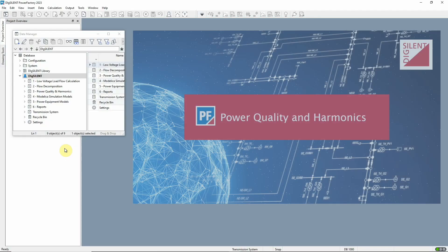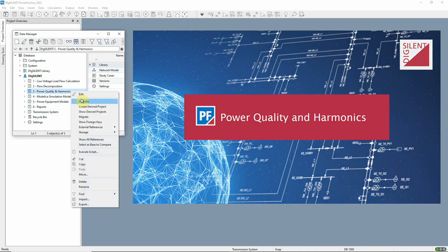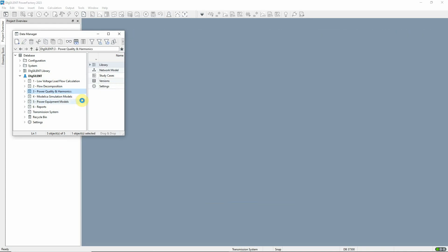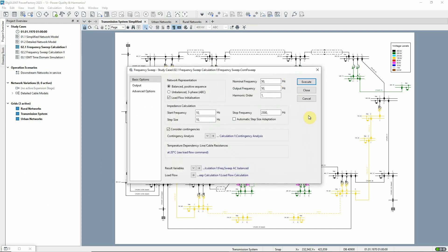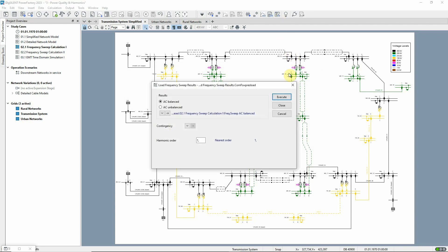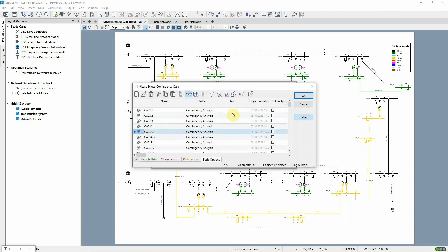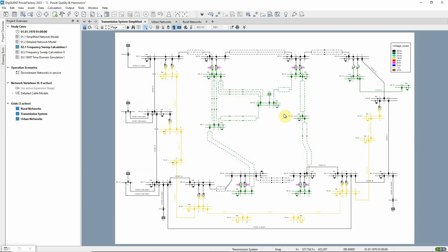The power quality and harmonic analysis module offers a number of developments in PowerFactory 2023. Both the harmonic load flow and the frequency sweep calculations now offer the possibility to include contingency analysis. With an expanded set of reports and a new option to reload results into memory, the results of the calculations can be examined in detail. And for both the harmonic load flow and the frequency sweep, a command is now provided for the automatic creation of plots.